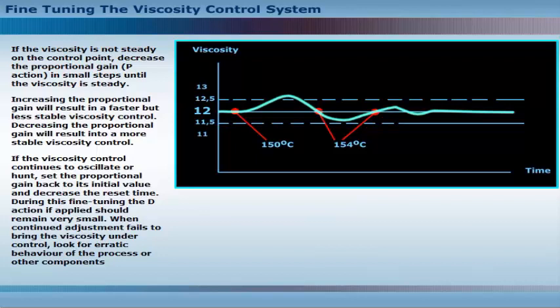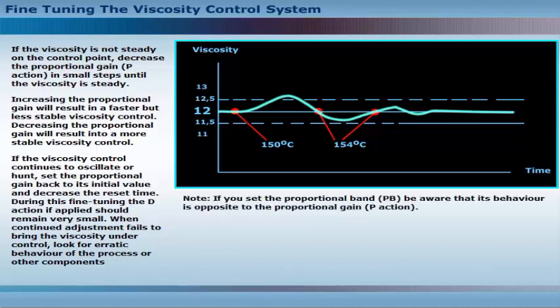During this fine-tuning, the D-action, if applied, should remain very small. When continued adjustment fails to bring the viscosity under control, look for erratic behavior of the process or other components. Note: if you set the proportional band, be aware that its behavior is opposite to the proportional gain.